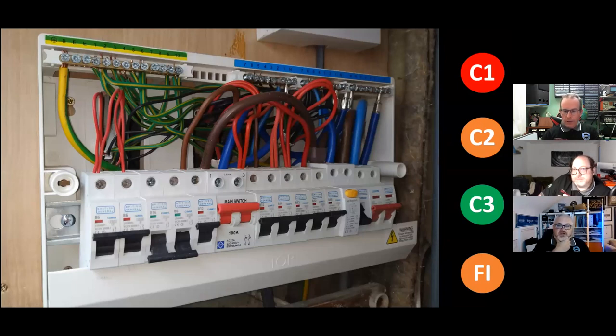This is John Ward's board again, isn't it? This is the same one with the gas pipe in front of it we saw before. Hey, you've got it off. Now we can see what's inside. And pay attention to what types of devices are actually installed inside this, what was a twin RCD consumer unit. So we've got a main switch replaced for an RCD. Yeah, it was a twin RCD, a BG1, and then the left RCD has been removed, and someone's put a switch in there instead. So a Lewden main switch. Yeah, which is a modern one because it's got torque setting on it, so it's pretty recent.